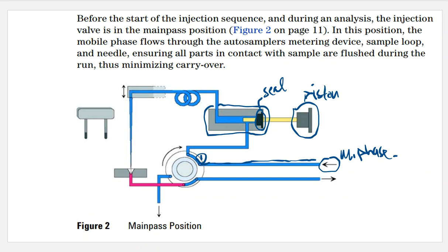And we do. So that has a tubing line that goes here at the bottom and one here at the top. So we've also talked about that top line. Where does that come from? What's its purpose? We said that that is the needle seat, and the needle is right here. And up on top, we have a tubing line that goes round and around in order for this pump to suck sample up out of the HPLC containers.